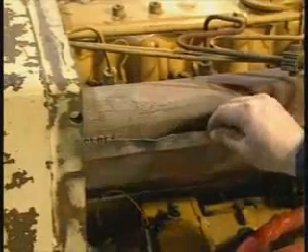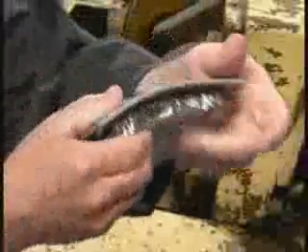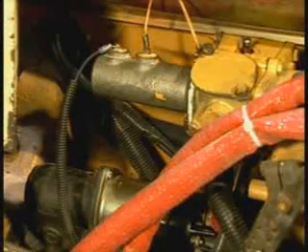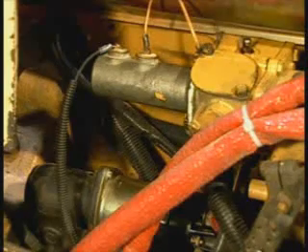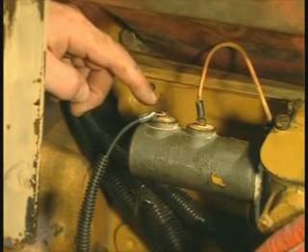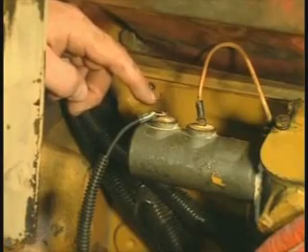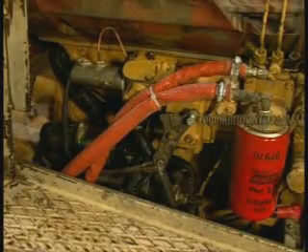Due to the inadequate size of this deflection shield, diesel fuel could come in contact with the hot exhaust manifold or exhaust pipe. Additional protection, such as ceramic coating or a jacket on the exhaust manifold and exhaust pipe, or flame-resistant sleeves or conduit on the hydraulic hoses, should be used. The new regulation will require each ungrounded conductor to have insulation compatible with the impressed voltage. The insulation materials must be resistant to deterioration from engine heat and oil. The ungrounded positive lead on this solenoid needs additional insulation. All wiring must have adequate mechanical protection to prevent damage to the cable that might result in short circuits.